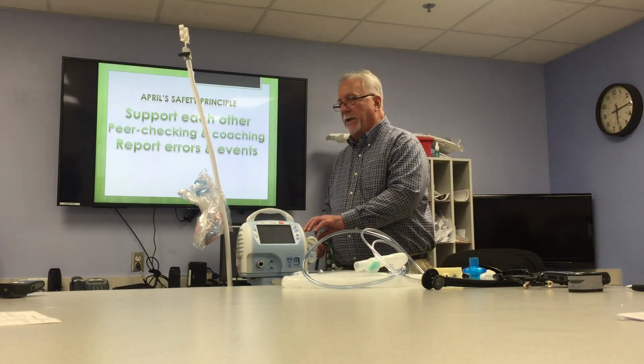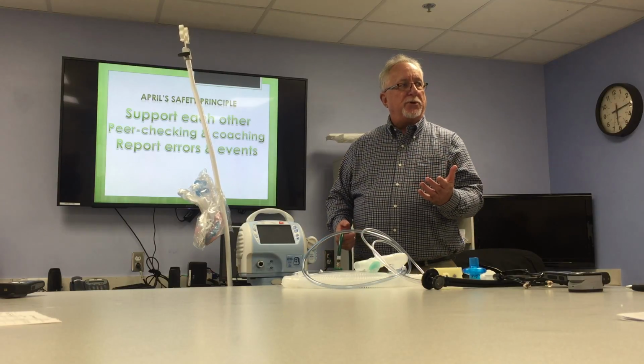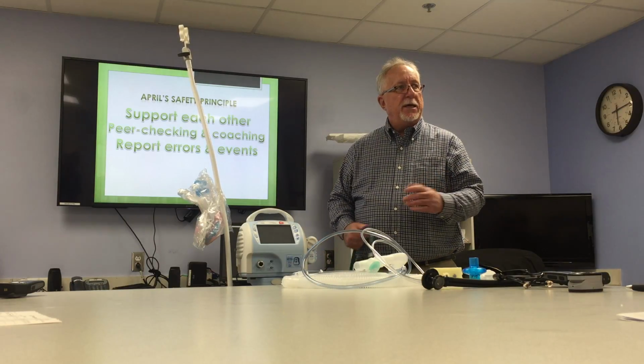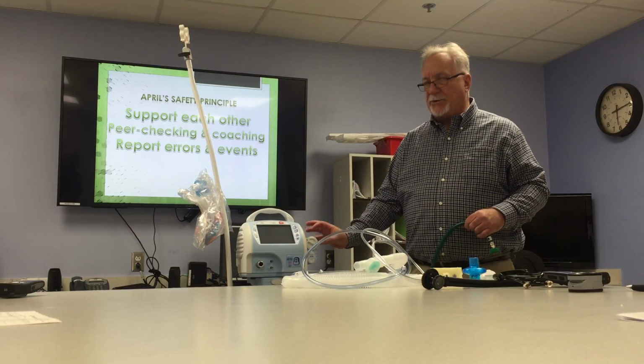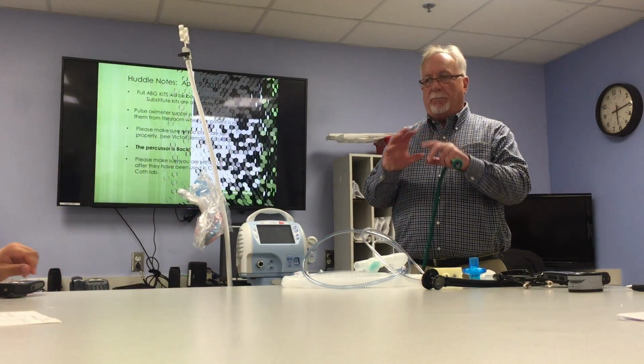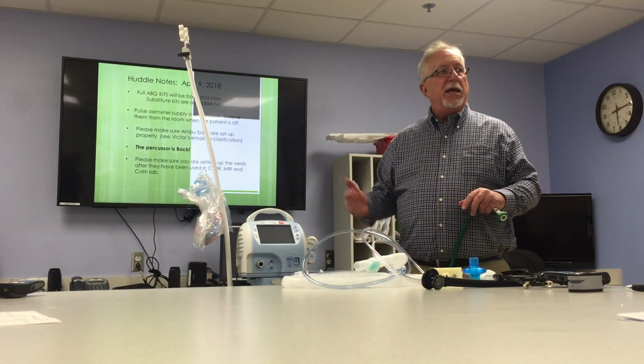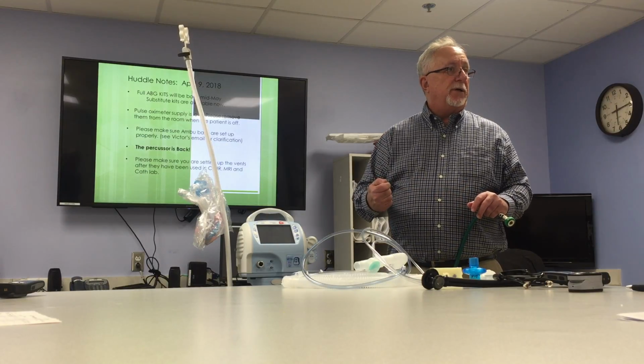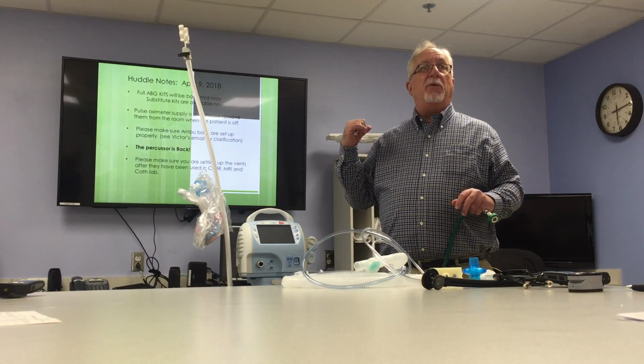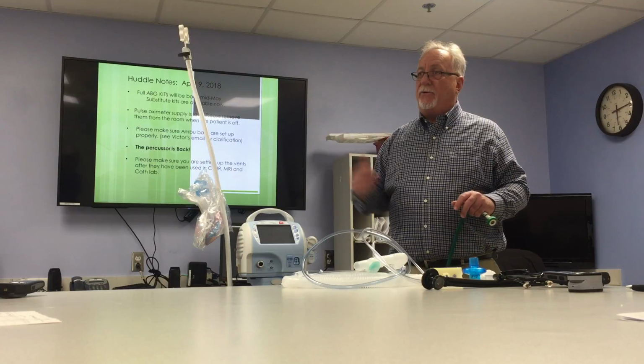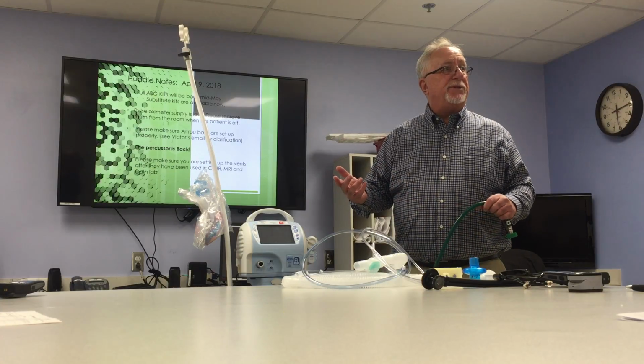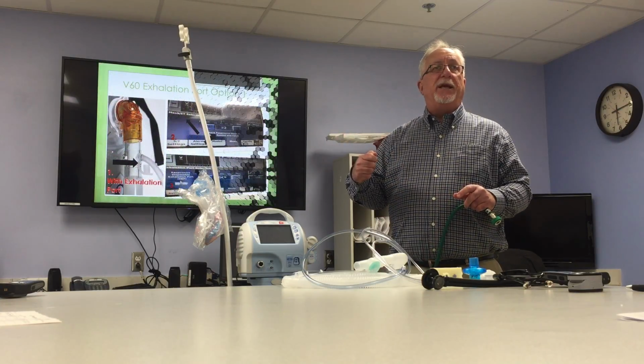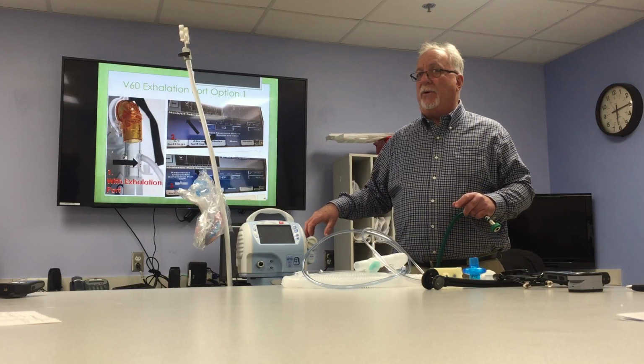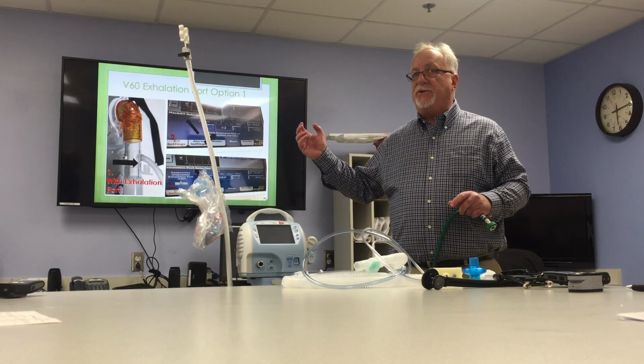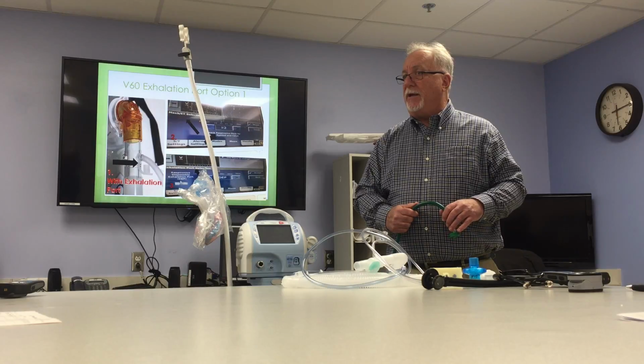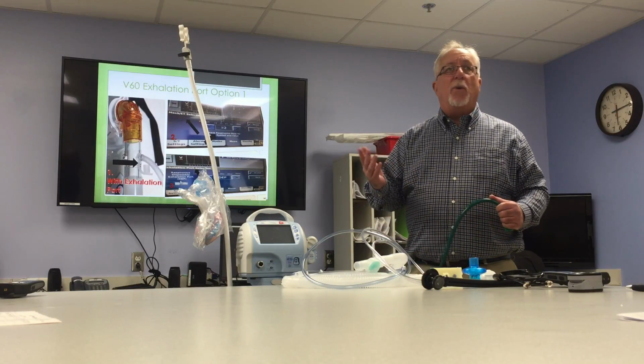There's also, and again, these ventilators were purchased for emergency preparedness, there's also an attachment on here. It's just kind of a round ball that screws onto the side, and you can do liter flow. So if your PSI would go out, your internal gas system would go out, and all you had was tanks, you could then just bleed in liter flow into the ventilator and it would deliver that. You would just adjust your liter flow to get whatever FiO2 you needed. Okay? So it goes either way.